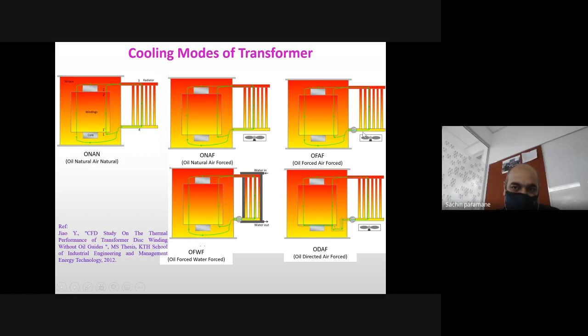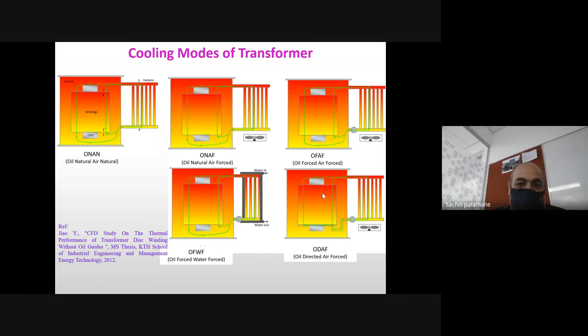Next cooling mode is, if load on the transformer increases further, oil forced and water forced. Now water is used as a cooling medium instead of air, so that the heat transfer coefficient will be higher, and a large amount of heat can be dissipated in the water. So this is oil forced, water forced. And last is oil directed air forced. That means oil is directed to move over the winding. So these are the basic cooling modes which are used for the cooling of a transformer.